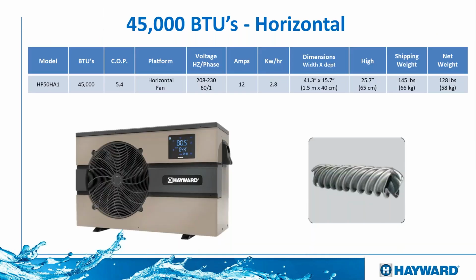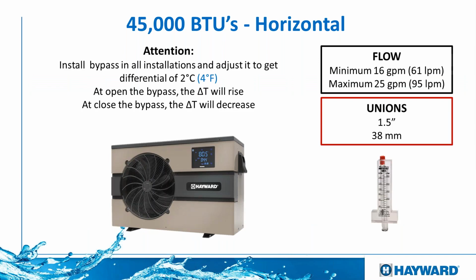Now going a little bit more into detail about the horizontal unit. Remember, this is a 45,000 BTU unit. The big advantage that it has is that it allows installation where you normally wouldn't be able to get a standard heat pump. And this unit can also be installed similar to a mini split AC, where with brackets you can hold it and install it next to a wall, for example. Also keep in mind that all of these units have a titanium heat exchanger, so we don't lose anything when it comes to longevity with this unit.